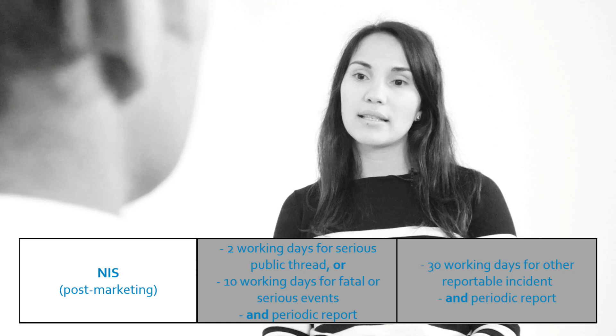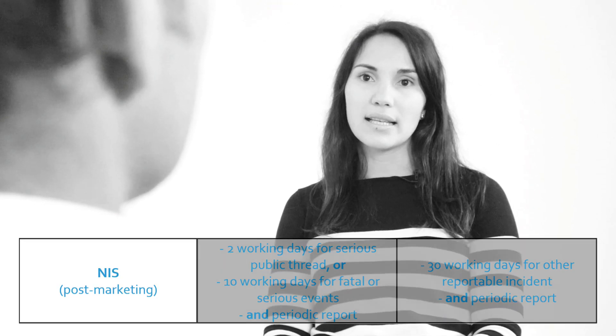For post-marketing studies, serious adverse events — also called incidents — must be reported within two working days when causing a serious public health threat or a new finding. Events causing death or unanticipated serious deterioration must be reported within ten days, and any other reportable event within 30 days. Under the MDR, that 30-day window will be reduced to 15 days, making timelines twice as short. Other reportable events include serious adverse events meeting seriousness criteria such as hospitalization or body impairment.